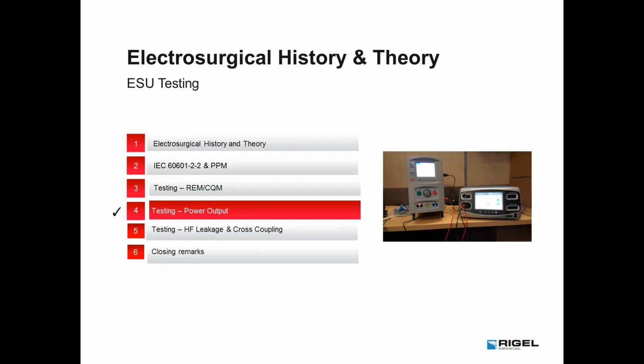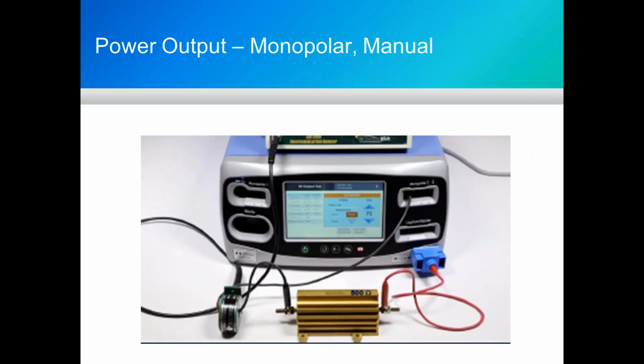So we're going to do some power output testing now. And for those who have gone to the Covidien school, typically you would use separate power resistors, low inductance power resistors, because impedance will always make a difference. We always talk about resistance as just DC resistance, but with a generator operating at 435 kilohertz, any inductance, any capacitance in your test circuit will impact the impedance that the generator sees, and that would also impact the readings that the analyzer will report. And if you have a lot of inductance, your power outputs, your currents will actually be higher than what they should be.